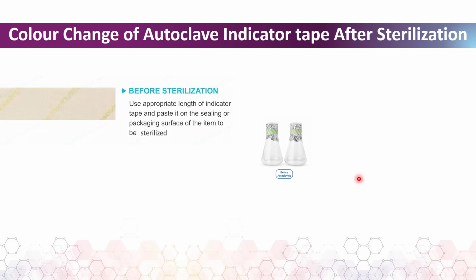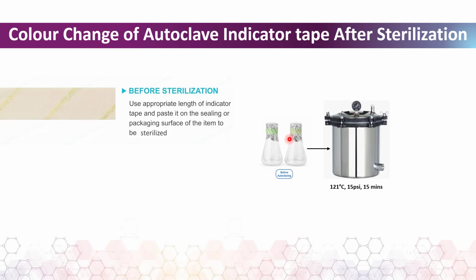Now let's look at the color change of autoclave indicator tape after sterilization. Even before sterilization, what we first have to do is to use an appropriate length of the indicator tape and paste it on the sealing or the packaging surface of the items to be sterilized. In this case, this is the item that we want to sterilize. And once this is done, we place it in an autoclave to sterilize it.